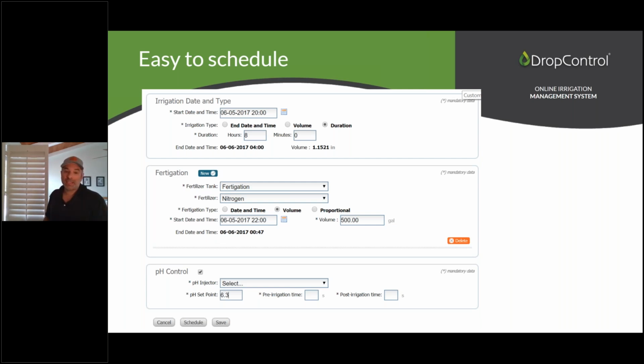With acid injection, we also have the capability of monitoring the pH and controlling the speed of the pump injection, maintaining a certain pH in the water at all times without having to guess or inject acid based on a simple water sample. We're constantly monitoring the pH and injecting acid based on the actual need.